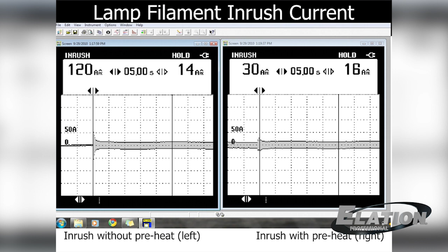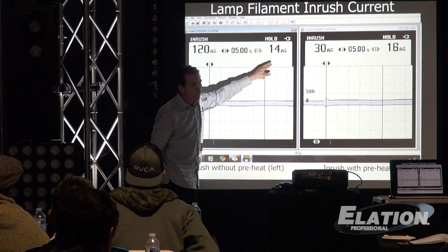And so the next day he brought in I think it's a 2K Fresnel, and we hooked it up to my power quality meter, which measures inrush current, and we turned it on 2 different ways. On the left-hand side, we turned it from completely off to completely on. So the filament goes from room temperature to operating temperature like that. And what you can see from this is that the inrush current was 120 amps. And the normal current is 14 amps. So it immediately pops up to 120, which is right here, and then it drops down and it levels off at 14 amps. That's with no preheat.